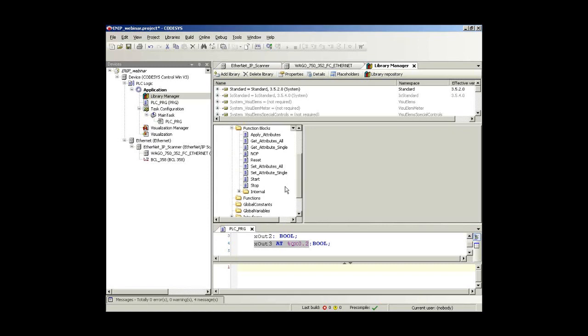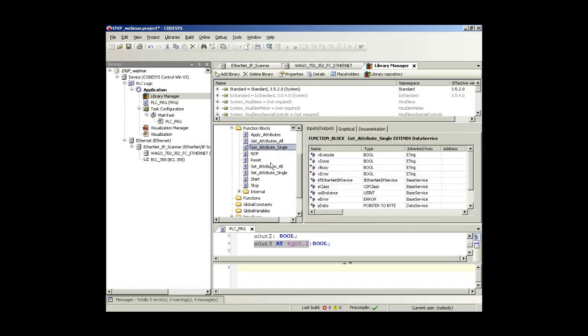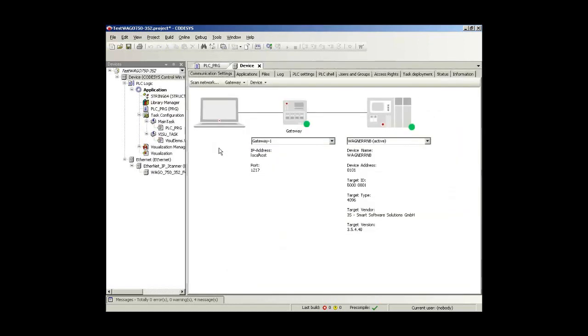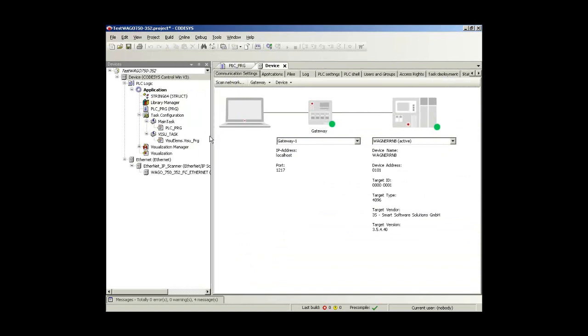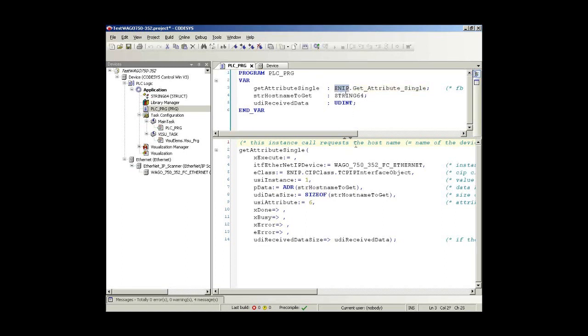And of course function blocks which you can use in order to access EtherNet/IP. And one thing we will use right now is GetAttributeSingle. This is a function block which gives you the access on attributes on the adapter, for example. In order to make it short, we have prepared that in the special project. You see this is very similar to that I had before. The only thing is that we make an instance of that GetAttributeSingle function block out of the EtherNet/IP services library.